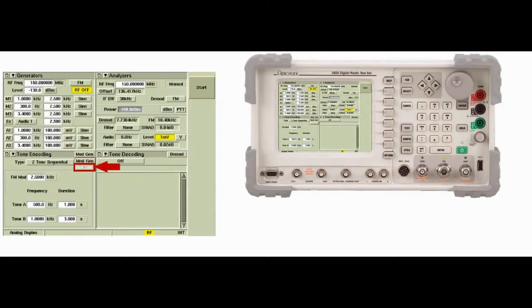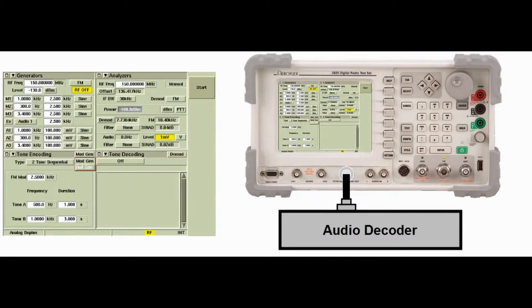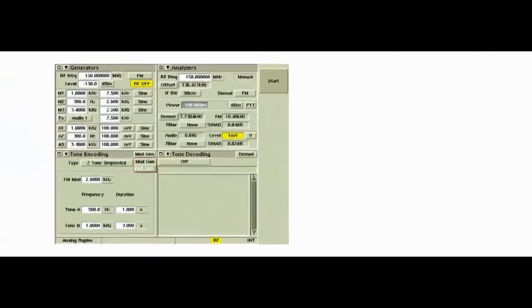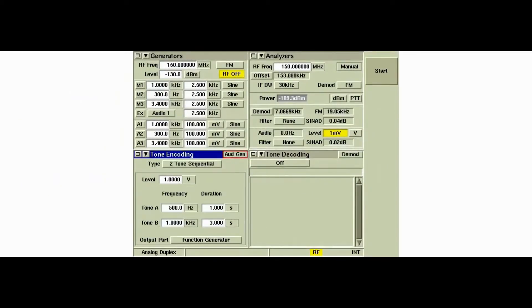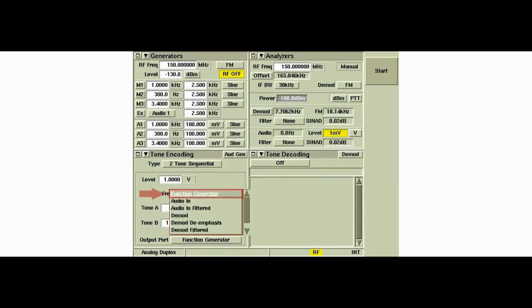When Audio GEN is selected as the output, the instrument generates the encoded signal as baseband audio. The FUNCTION GEN DMOD OUT connector is used to output the audio signal. When the output is set to audio, the output port button is displayed on the tone encoding tile. This button is identical to the output port button found on the EXPANDED GENERATORS tile, placed here so the audio output can be conveniently set to FUNCTION GENERATOR for audio tone encoding.